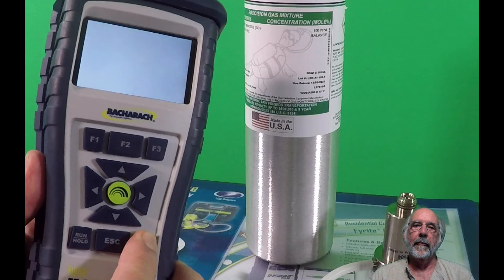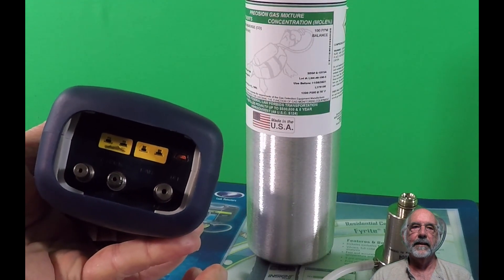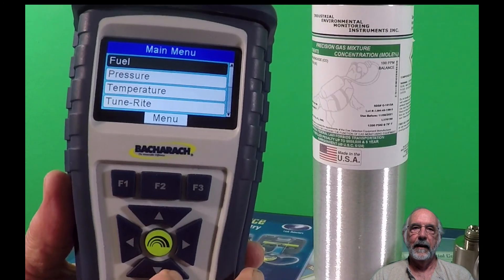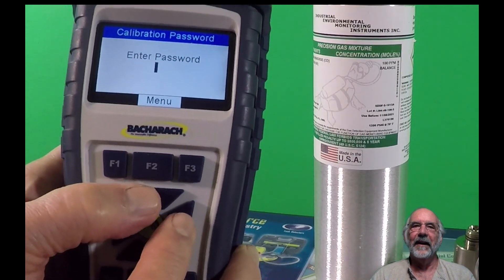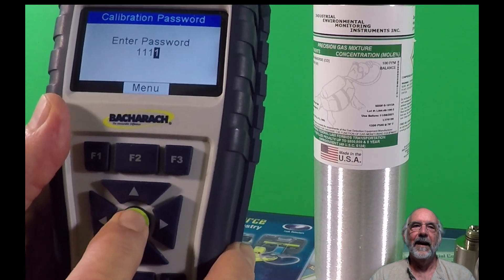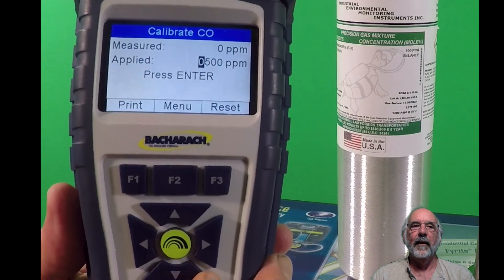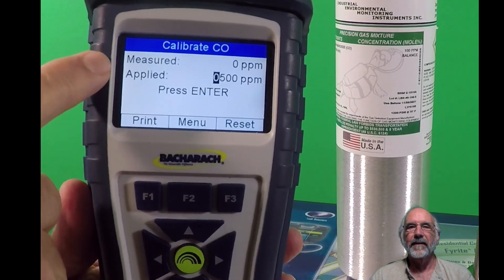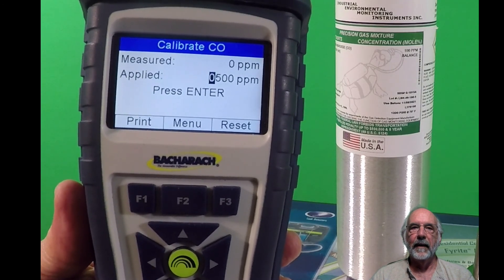You start by turning on the instrument. You do not need to have the hose attached, and you will get a thermocouple error message as the thermocouple is not plugged in. Once the instrument is warmed up, go to the calibration screen. It will ask for a password — the default password is 1111. You can change that through the Fyrite user software. Scroll down to CO calibration and press the round enter button on the keypad. The display will show 'measured' and 'applied.' The measured reading is what the instrument thinks it's seeing; the applied number is what we know it should be seeing, and it should match the ppm content of the gas cylinder.